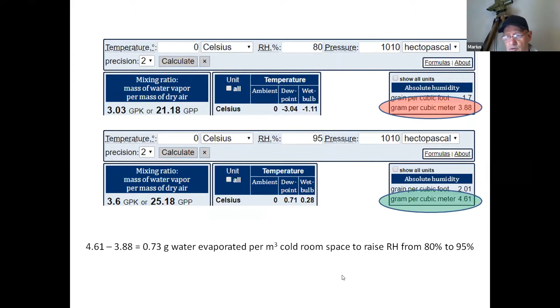So yes, you can buy a humidifier and you can go and humidify the air by adding 0.73 grams of water for every cubic meter of cold room space, and that will raise your humidity from 80% to 95%. That's what you could do. The question, however, is why is this only 80% in the poor cold room? Is it a design fault from an engineer that didn't take into account the fact that you wanted 95%?